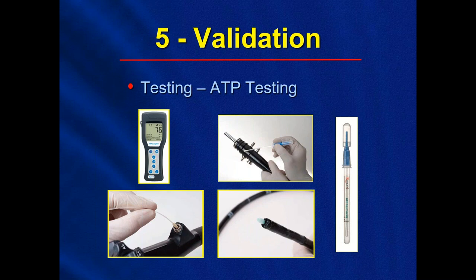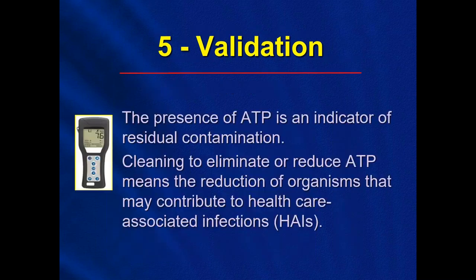Now, understand that devices that fail the ATP test will need to be re-cleaned and retested before final high-level disinfection and sterilization. So the presence of ATP is an indicator of residual contamination. Granted, we don't know what that contamination is. We're not culturing, so we don't know what's growing. It's just telling us that there's something there that shouldn't be there. Cleaning to eliminate or reduce ATP means the reduction of organisms that may contribute to healthcare-associated infections. Again, the ATP measurement, it's an excellent means of verifying that your cleaning processes have been effective.